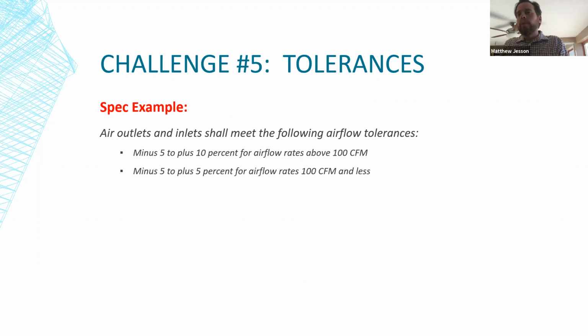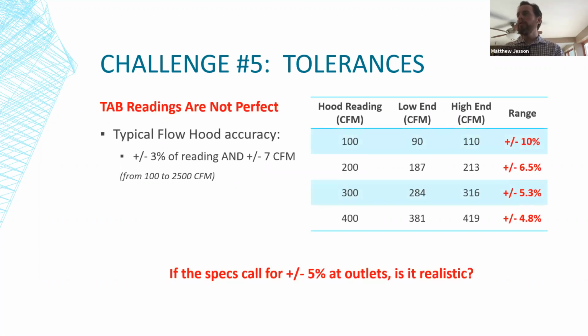And here's one that is really popular with a certain federal government agency. It says air outlets and inlets shall meet the following airflow tolerances: -5 to plus 10% for airflow rates above 100 CFM, -5 to plus 5% for airflow rates 100 CFM and less. Now, going back real quick to our chart here, I should point out that the published accuracy of this flow hood doesn't state anything below 100 CFM. And if you look at the trend of these numbers, it's not getting better as it gets lower. So you can probably guess that when you're below 100 CFM, at best, you're plus or minus 10% just for the accuracy of the hood.